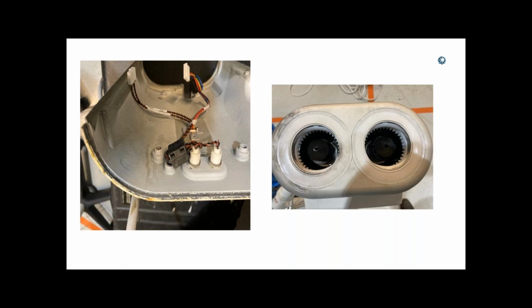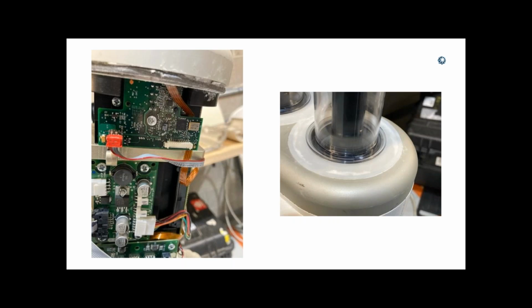All that is contrast. And the contrast sitting there will actually eat away at the metal. The metal will become brittle and actually snap off. All that white in there is contrast. Even down in there, you can see contrast. That's what a good PM does. That's what it gets rid of. There's another one, contrast. All that white, that's contrast up under the seals. That's why you get those cap seals in your PM kit, because they're very, very difficult to take off. There's a trick to it, but they're difficult to take off.